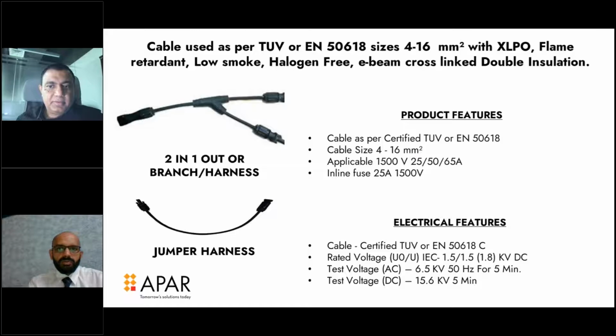For the TUV 4 to 16 square mm cables which are used, we can offer a 2-in-1 out or branch harness or even a jumper harness. The features, as we can see, are TUV certified cables, an inline fuse of 25A, 1500 volt. The electrical test features are a test voltage of AC 6.5 kV, 50 Hz for 5 minutes, and DC 15.6 kV for 5 minutes.